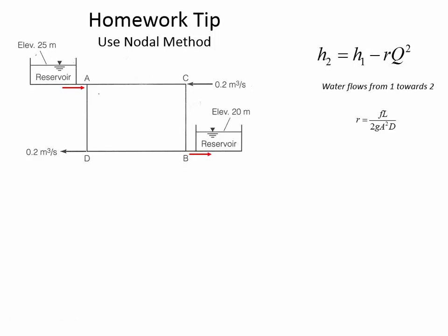In the problem, you'll have all the information you need except the F value to calculate R. If you don't know the flow rate, you can't calculate velocity, so you can't calculate the Reynolds number, and you can't calculate F. But you have to solve the problem anyway — you can't just write 'don't know the velocity, can't find F.' The shortcut is the fully turbulent flow assumption.